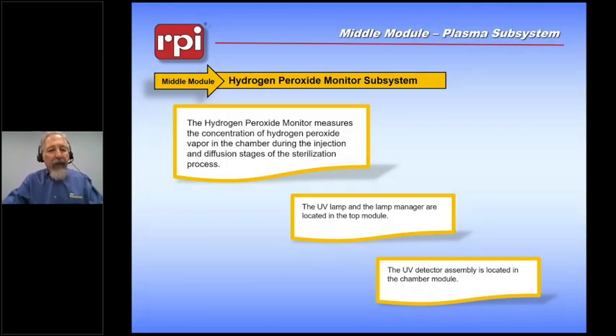The middle module also contains the hydrogen peroxide system, as we talked about earlier. The hydrogen peroxide monitor uses a UV light to measure the transmittance through whatever material is in the chamber. The UV detector is located on the bottom. The light is located at the top.